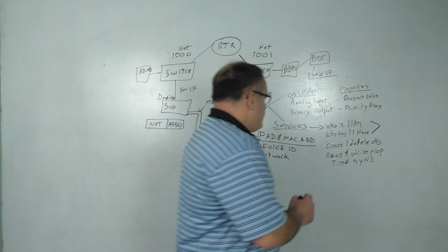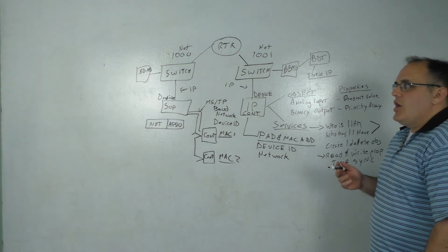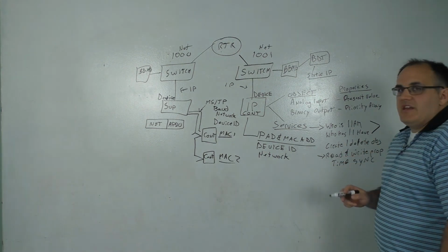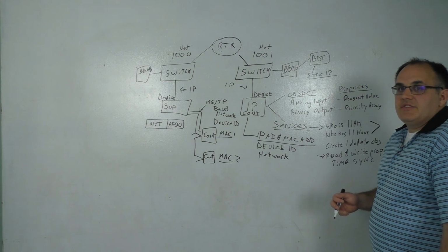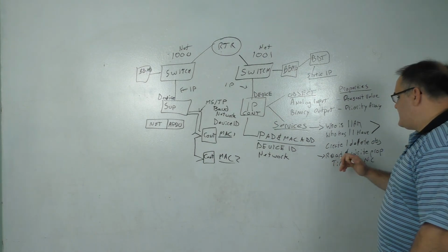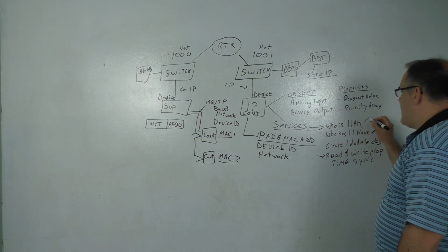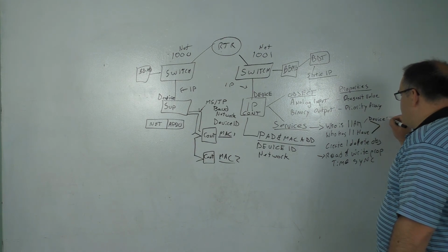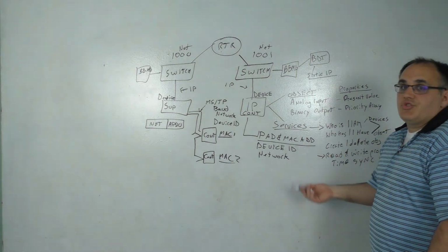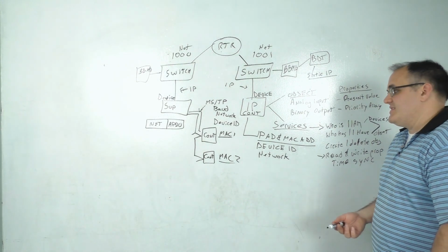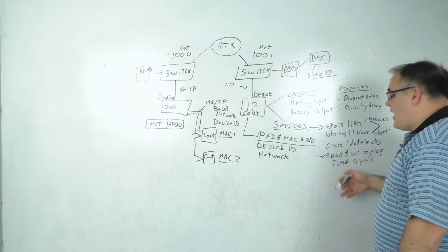Once it's done that, it can then go and use read and write properties. Now, that's not 100% of the time. You don't always have to create an object before you can do read and write properties. You can simply do who is and then do a write to a property once you know. But basically what's going on here, so we've done who is, I am, who has, I have. So who is, I am is for devices. Who has, I have is objects. Create, delete objects. A device is an object. A trend is an object. So whenever you're creating alarm extensions, trend extensions in a pure BACnet system, you're running this create service. Then you have read and write properties.